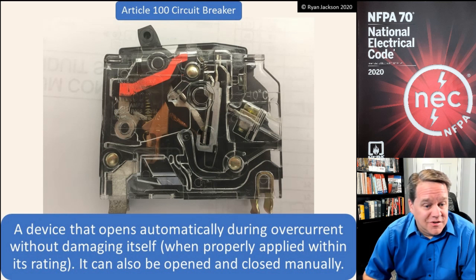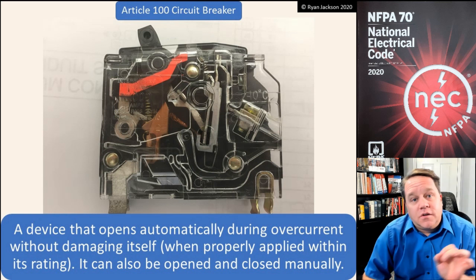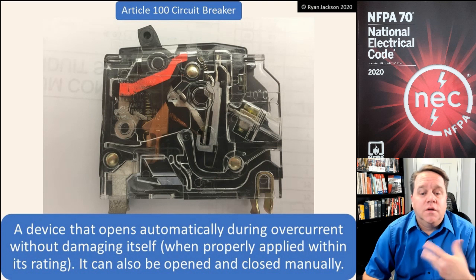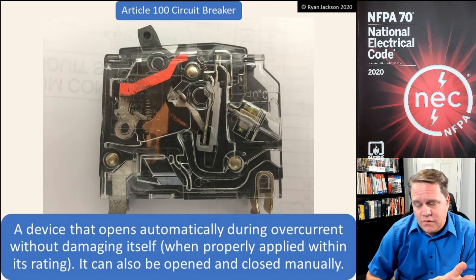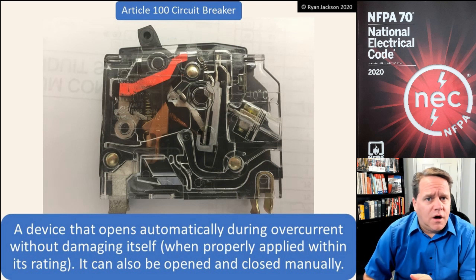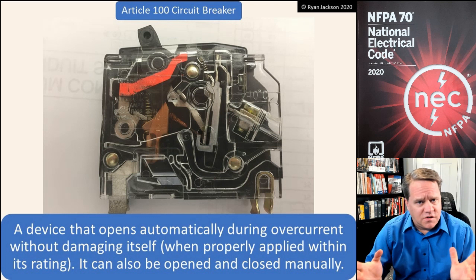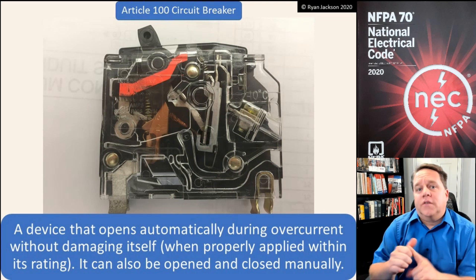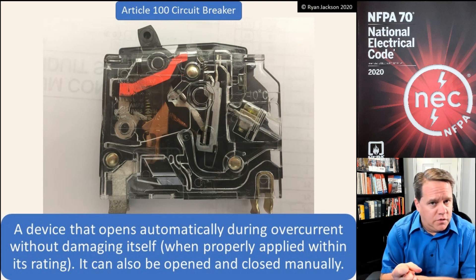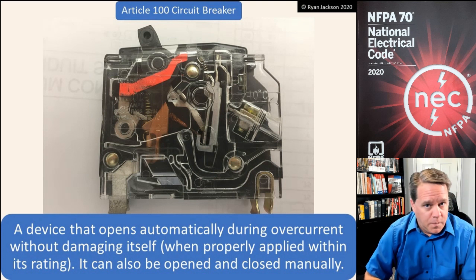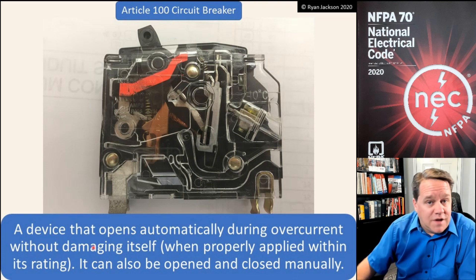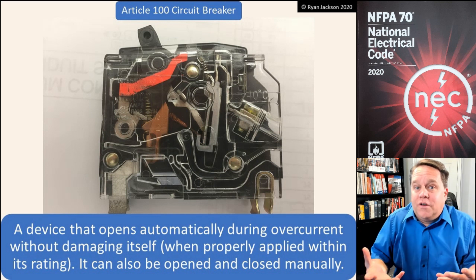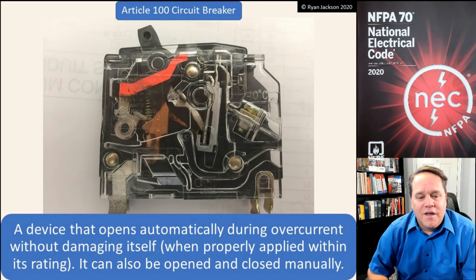Article 100 circuit breakers. A circuit breaker is a device that opens automatically during overcurrent without damaging itself when properly applied within its rating. Overcurrent is a ground fault, a short circuit, or an overload — any of those three will cause a circuit breaker to open generally without damage to itself. If the circuit breaker clears a fault but explodes, what did we really solve? So without extensive damage to itself.